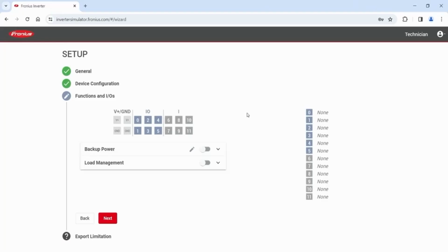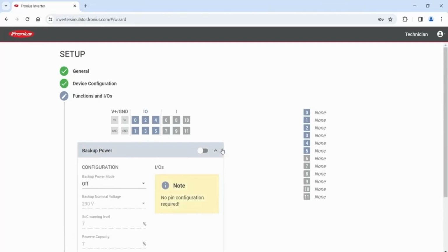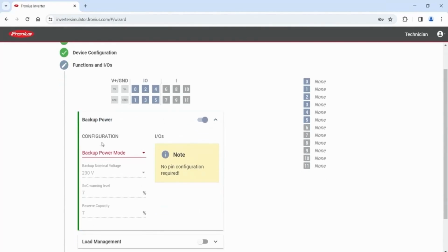For the commissioning of the PV point comfort, the last thing that we need to do now is to connect to the web interface of the Gen24 Plus and activate the PV point there. To activate the PV point comfort and do the commissioning, you can directly enter the settings on your inverter, or during initial commissioning, you can enter the PV point function and IOs. Here you will find the PV point backup power, and you can open the setting and activate the backup power by clicking on this switch here. After that, you can switch the configuration mode and you can switch here to PV point. And afterwards, please set the correct voltage depending on your region.